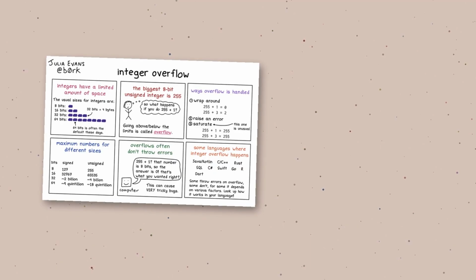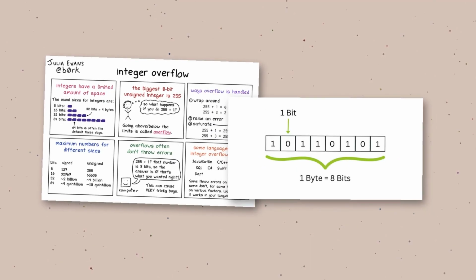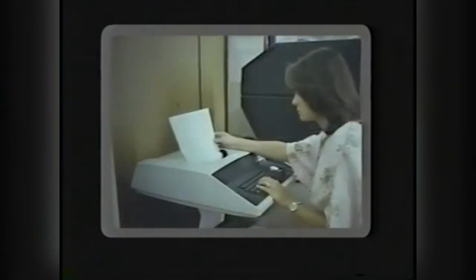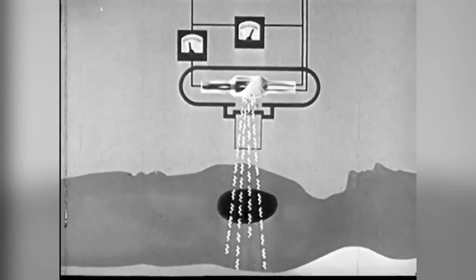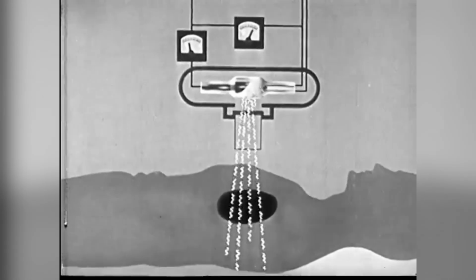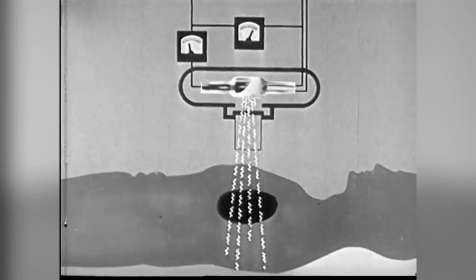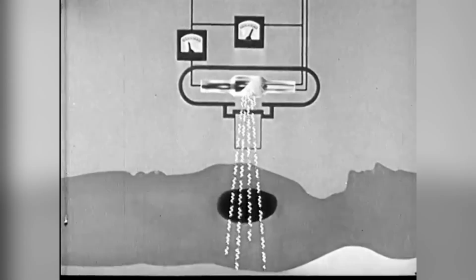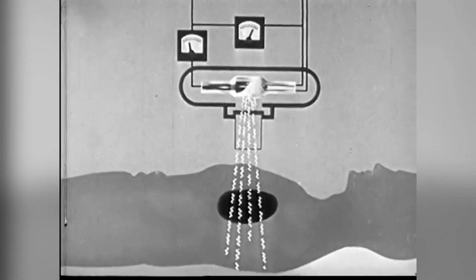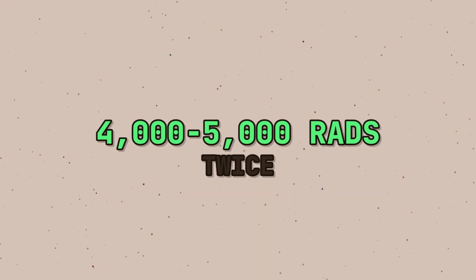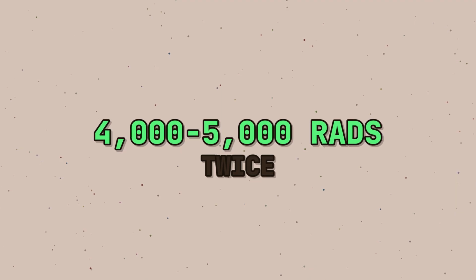Setting up the machine ran a routine that incremented a 1-byte counter on every pass, several hundred times per setup. 1 byte holds a maximum of 255, so on every 256th pass, the counter rolled over to 0, and a 0 told the rest of the program that the upper collimator had already been checked and was fine. Pressing the set button at exactly that instant, the operator turned on a full 25 million electron volt beam with the turntable still in the field light position. No target, no flattener, no scanning, and a stainless steel mirror directly in the path.